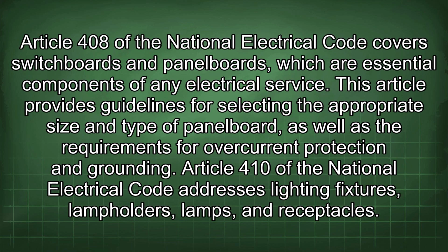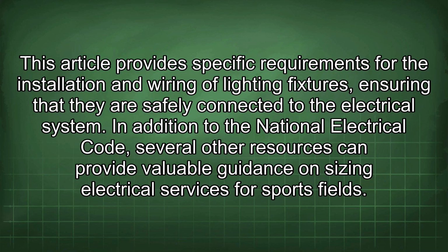Article 408 of the National Electrical Code covers switchboards and panel boards, which are essential components of any electrical service. This article provides guidelines for selecting the appropriate size and type of panel board, as well as the requirements for overcurrent protection and grounding. Article 410 of the National Electrical Code addresses lighting fixtures, lamp holders, lamps, and receptacles.